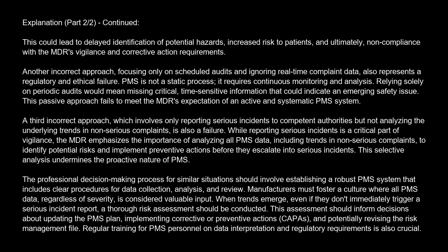and corrective action requirements. Another incorrect approach, focusing only on scheduled audits and ignoring real-time complaint data, also represents a regulatory and ethical failure. PMS is not a static process. It requires continuous monitoring and analysis. Relying solely on periodic audits would mean missing critical, time-sensitive information that could indicate an emerging safety issue. This passive approach fails to meet the MDR's expectation of an active and systematic PMS system.